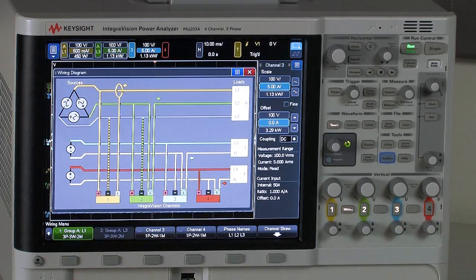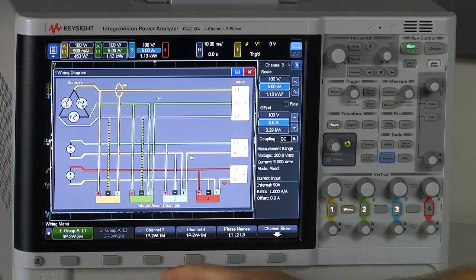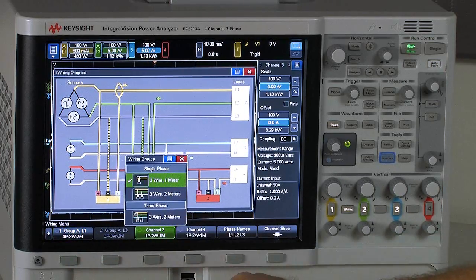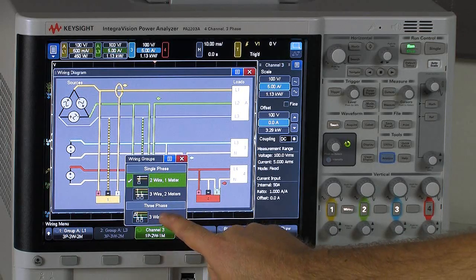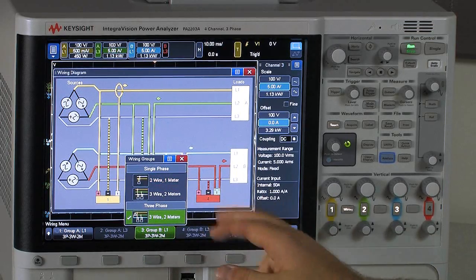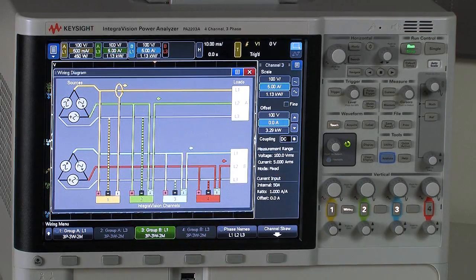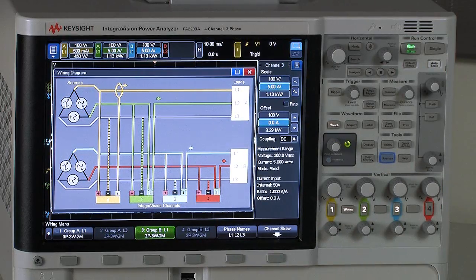So for example, I have channels one and two set up for that three-phase two-meter measurement. I can go over here and configure channel three and four again for a three-phase, three-wire, two-meter measurement. So in that way, for certain systems, I could actually characterize a three-phase in, three-phase out system.